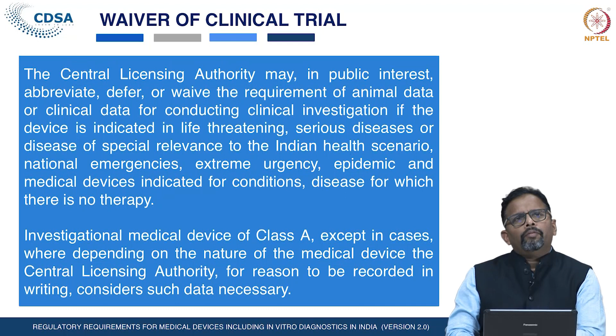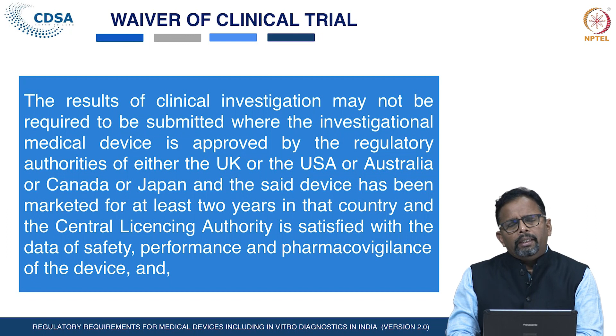The result of the clinical investigation may not be required to be submitted where the investigational medical device is approved by the regulatory authority of either the UK, USA, Australia, Canada or Japan, and the said device has been marketed in those countries for at least 2 years, and the Central Licensing Authority is satisfied with the data of the safety, performance and pharmacovigilance of the device, and there is no evidence of a theoretical possibility, on the basis of existing knowledge, or any other difference in the behavior and performance in the Indian population.